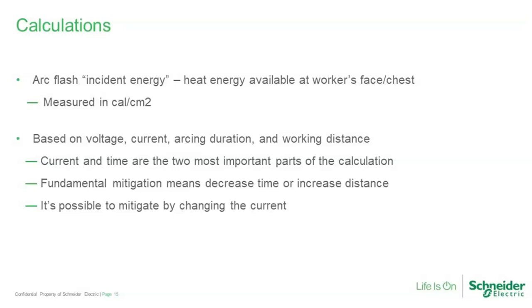Not that voltage is not important, but what we're looking at there is typical system voltage. If you're dealing with a power system that's operating at 480 volts, well, your voltage is 480. You're going to use that nominal value. That's kind of fixed, but fault current may vary depending on the size of the transformer feeding a portion of the facility, how much cable impedance is in place between you and the source, even the size or capacity of the utility that's serving the facility. So current, and then time is the other one.